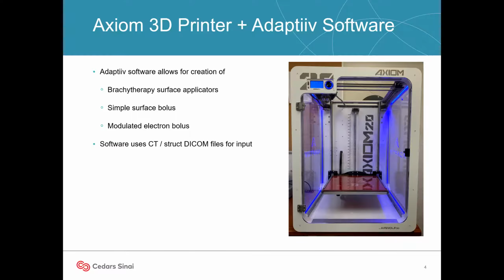The software uses the CT and structured DICOM files, and we can export from Eclipse and import into the Adaptiiv software, and then we can also export and import back into Eclipse, and this is how we can iterate to get pre and post plans to optimize our channel locations. The print material that we use currently is a Cheetah TPU filament. This is a filament that was both commissioned and tested by Adaptiiv as well as by our clinic.